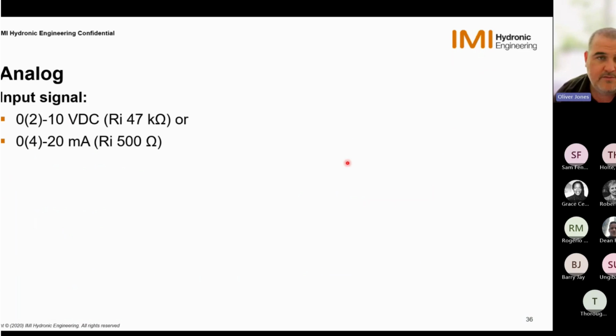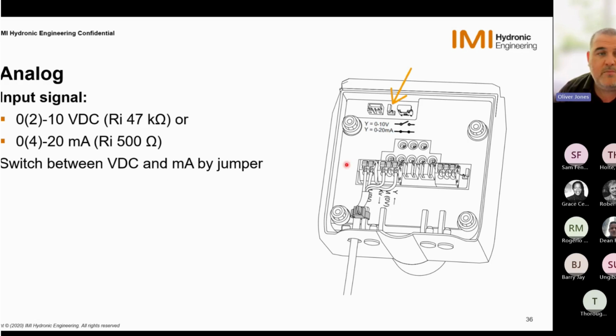Analog, again, 0 to 10 or 2 to 10 VDC, and 0 to 20 or 4 to 20 milliamp can also be used. We can make that switch with a jumper, which is internal on the valve itself. So if we lift the lid, take the 4 screws out and lift the lid off the Smart control box itself, we're left with a jumper, and with the jumper in the position that we can see here, it's in 0 to 10 volts as an input signal. All we would need to do to change that to 4 to 20 is literally lift the jumper and place it across the two contacts, so we actually make the bridge and connect the circuit itself.